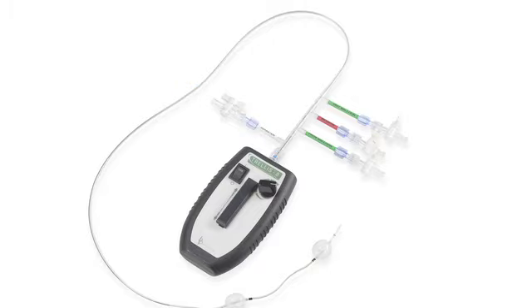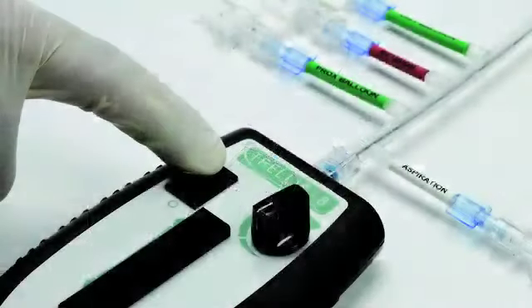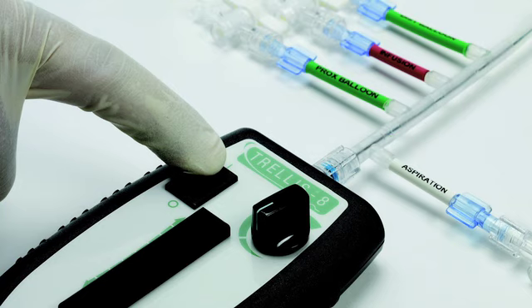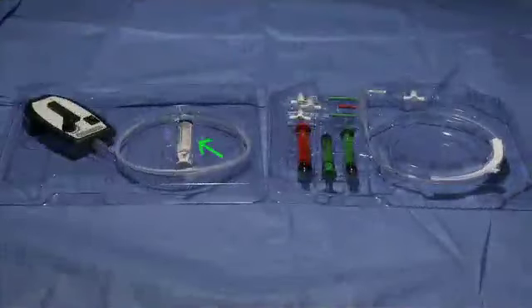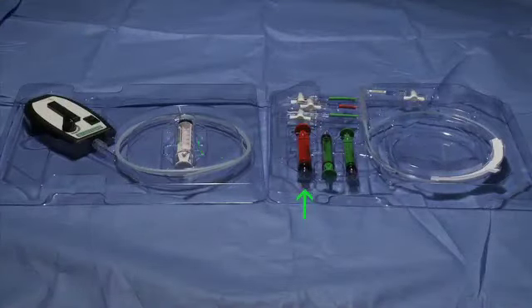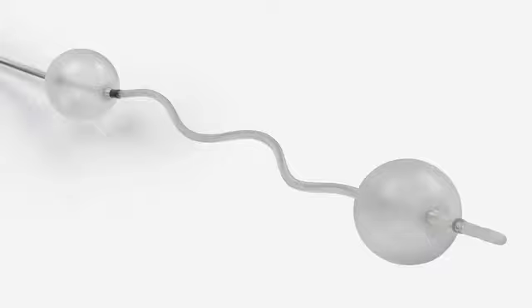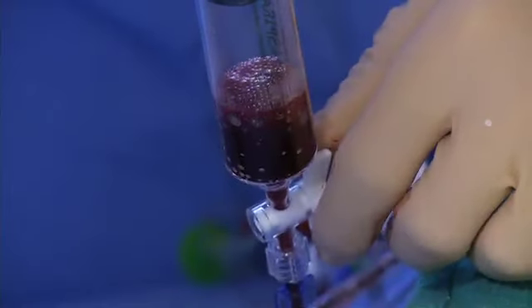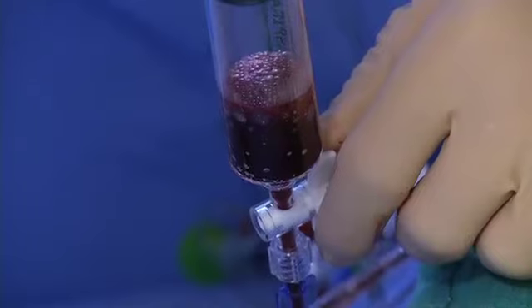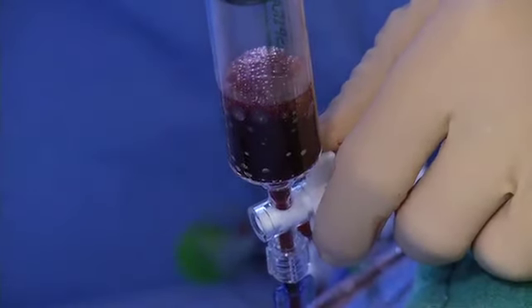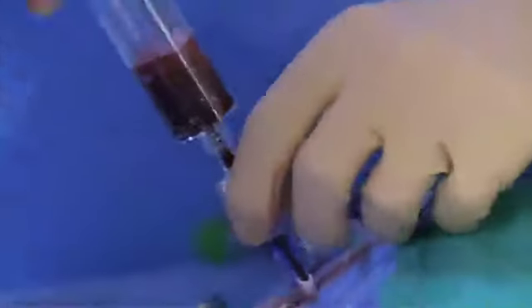The Trellis system includes an oscillation drive unit, or ODU, with an integrated dispersion wire, and also includes one 30 cc syringe for aspiration, one 10 cc syringe for infusion, and 2 6 cc syringes for balloon preparation and inflation. Infusion holes are present between the 2 balloons for the infusion of physician-specified fluids. The aspiration port allows for removal of residual physician-specified fluid, for example thrombolytic, and any dissolved thrombus through a 30 cc locking syringe, which is included with the Trellis system.